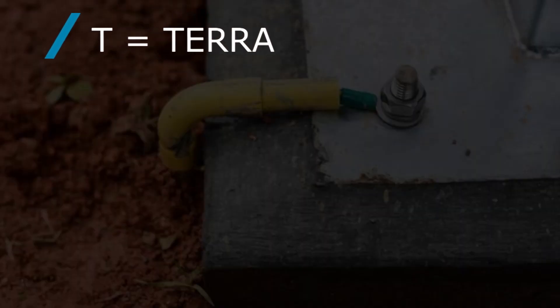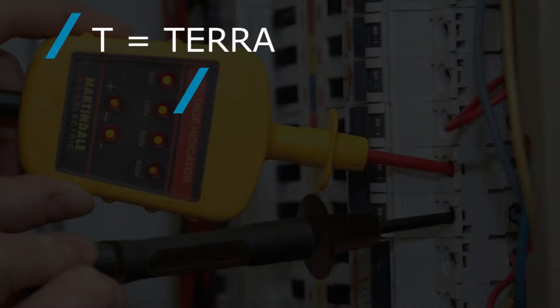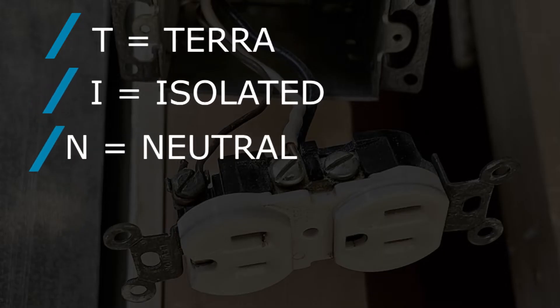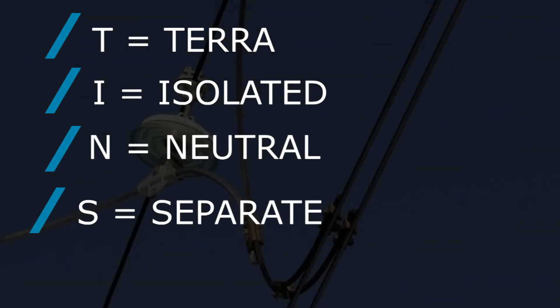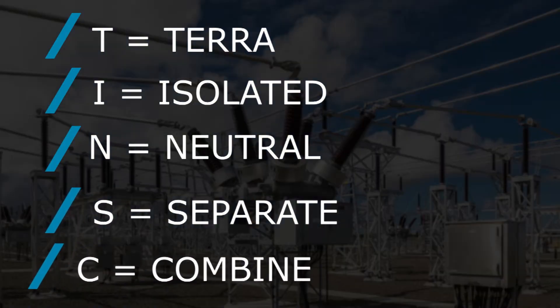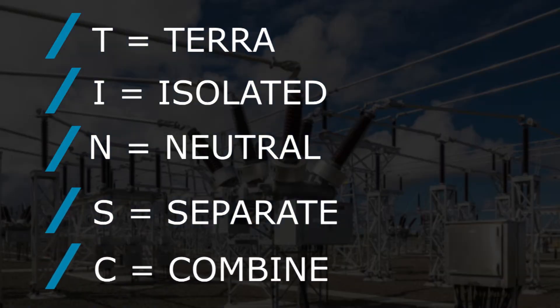But what do all these letters even mean? We're going to explain that now. T is the direct connection to the earth — T stands for the Latin word terra, which means earth. I is isolated, N is neutral, S is separate, and C is combined. Now we know what all the letters stand for, but how do they combine together? The first letter of each system refers to the power source from a star-connected winding. The second letter refers to the consuming equipment that needs to be earthed.